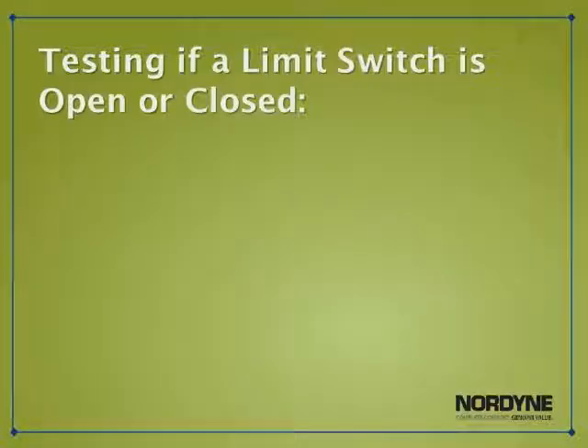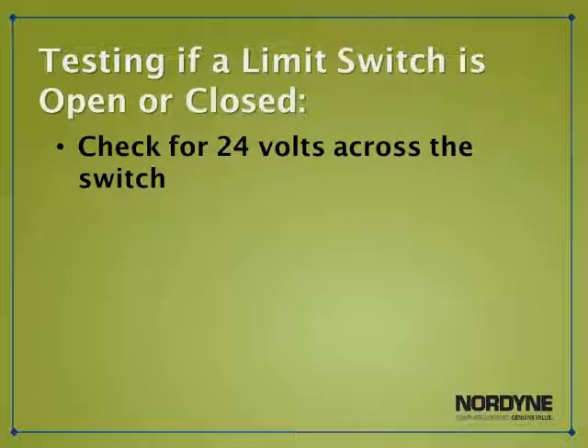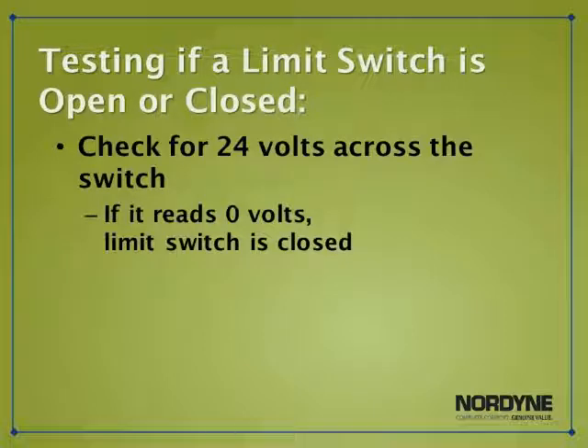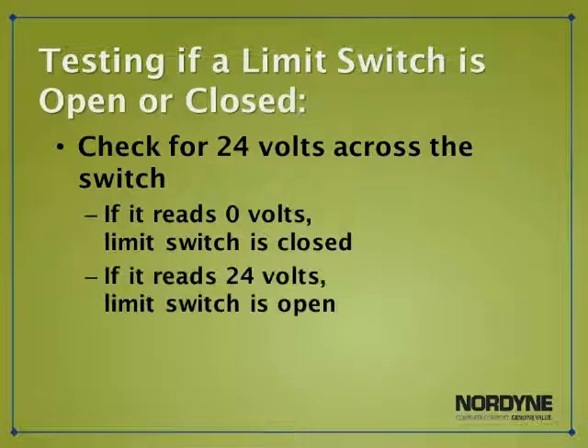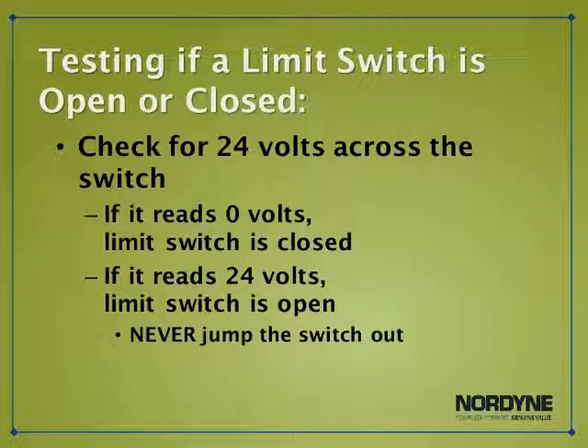The easiest way to check a limit switch to see if it's open or closed is to check for 24 volts across the switch. If you measure 0 volts across the switch, that tells me the switch is closed. If you measure 24 volts across the switch, that tells me the switch is open. If you find a switch that is open and will not close, never jump the switch out. This can cause the furnace to operate in unsafe conditions, which can damage your furnace or damage your home itself. You must replace the switch.